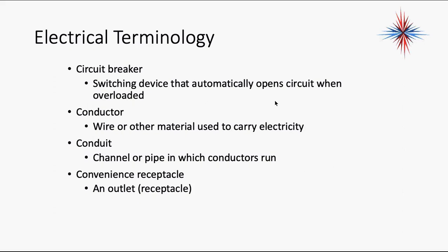I walked down into the basement, and they had a chair sitting in front of the breaker panel with a fan blowing air across the breaker panel. I'll probably post some pictures of that because this is a perfect example. The breaker panel was so hot when I touched it, it could have almost burned me. And that's how they were running their air conditioning.